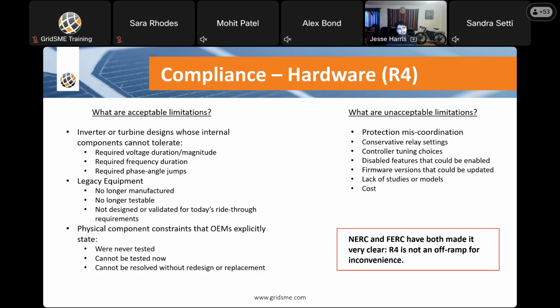I was on a call with GE, and they were talking about their wind turbines, and they made this very clear. There's no way the current ones that are out there, they can't test them. And it takes a lot to set one of those windmills up in a lab and test it. And so, what are unacceptable limitations? Protection miscoordination, conservative relay settings, controller tuning choices, disabled features that you could have enabled, firmware versions that could be updated. So all of those have one thing in common. They're all software. Software is not hardware. Also lack of studies or models, and then of course, cost. Big takeaway on this one, NERC and FERC have both made it very clear, R4 is not an off-ramp for inconvenience.